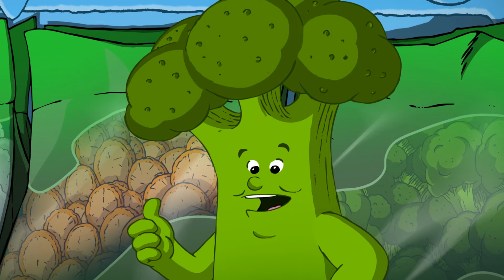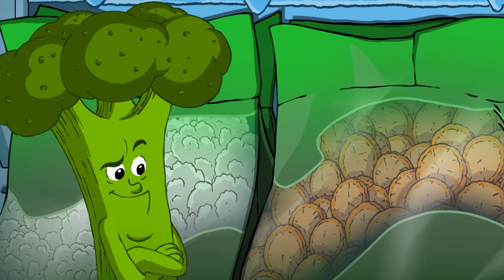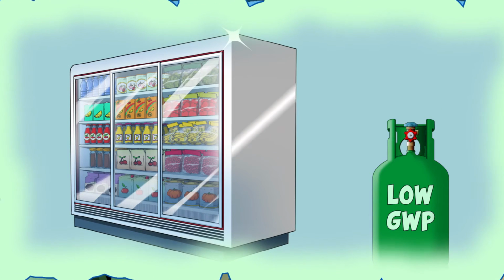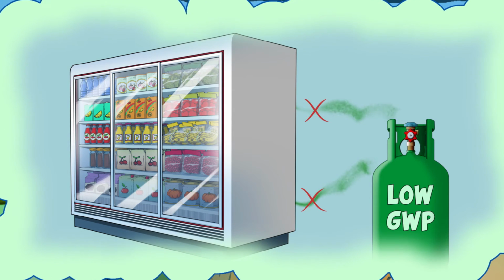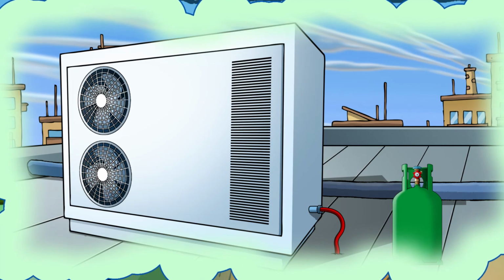So it's as simple as that? There are other important actions that will help ensure that sufficient refrigerants and other fluids are available. For example, as well as using lower GWP refrigerants for new and updated equipment, further action is necessary for leak prevention through design and maintenance. Where appropriate, charge sizes of refrigerant in equipment should be reduced. Recycling and reclaim of HFCs can always be improved.